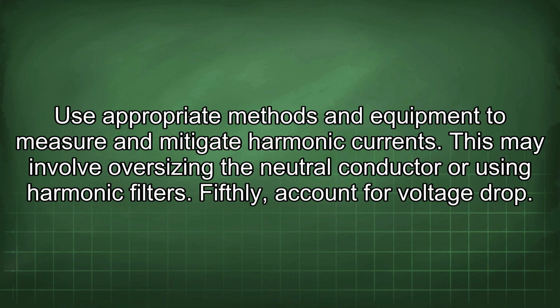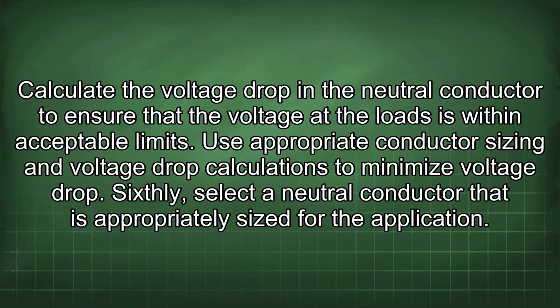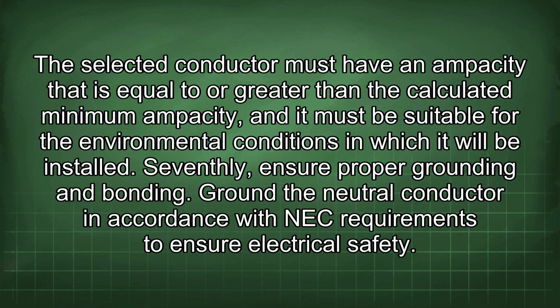Fifthly, account for voltage drop. Calculate the voltage drop in the neutral conductor to ensure that the voltage at the loads is within acceptable limits. Use appropriate conductor sizing and voltage drop calculations to minimize voltage drop. Sixthly, select a neutral conductor that is appropriately sized for the application. The selected conductor must have an ampacity that is equal to or greater than the calculated minimum ampacity, and it must be suitable for the environmental conditions in which it will be installed.